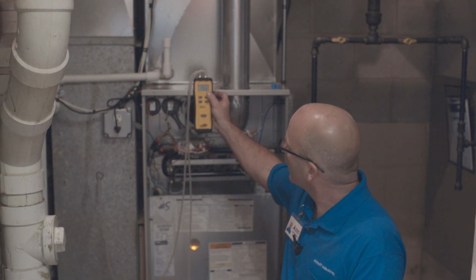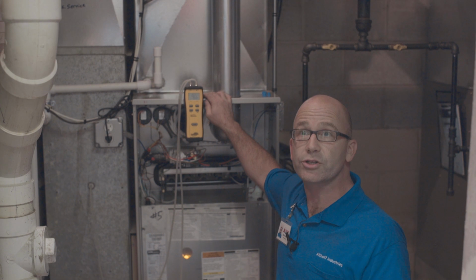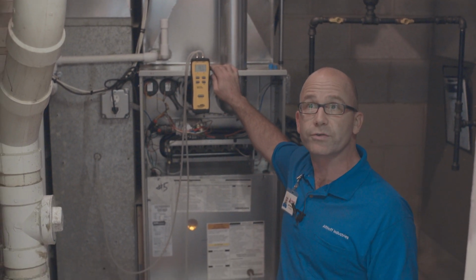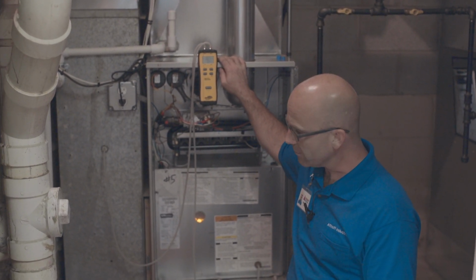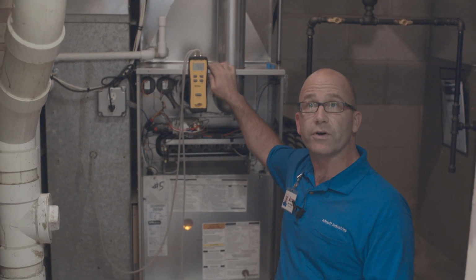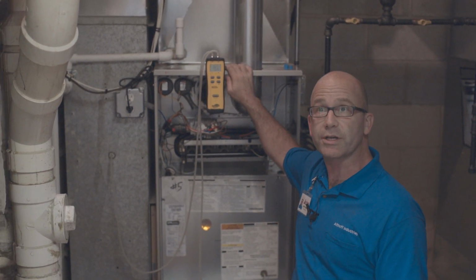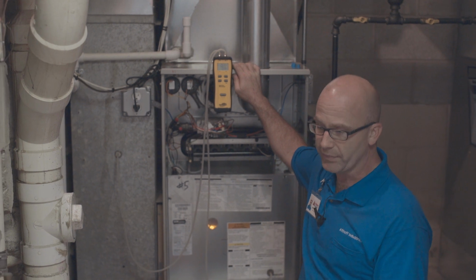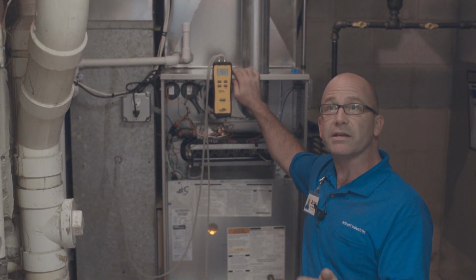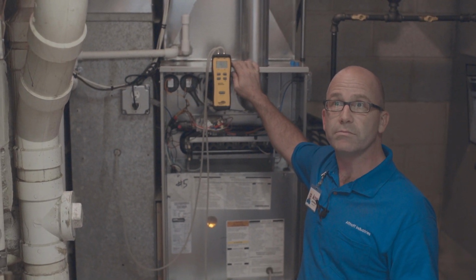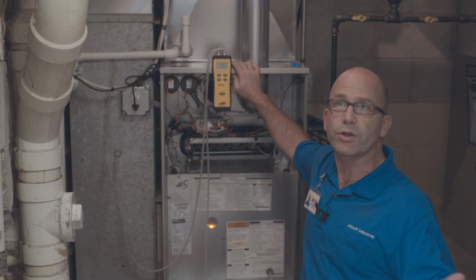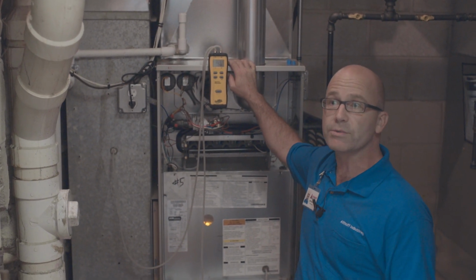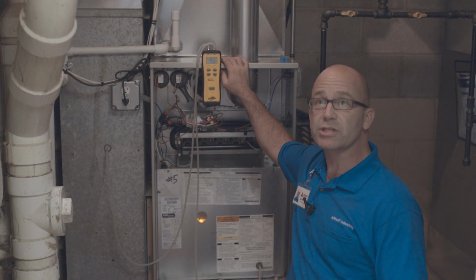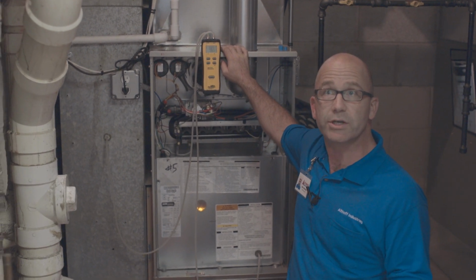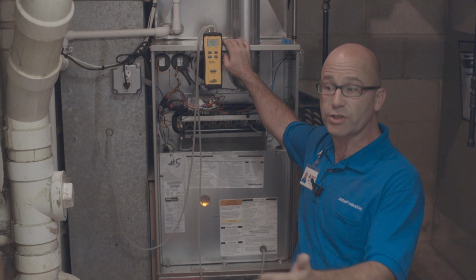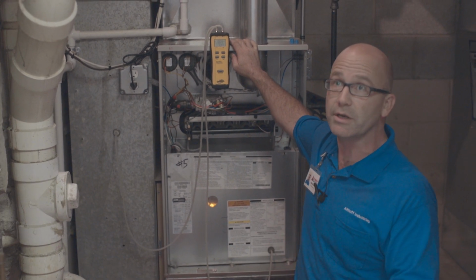There's kind of a joke in our industry. We call pleated filters sometimes super pleats. And all that means is the filter is good at catching dirt, particulate, and dust. It's great at that. But that also has a negative effect on the performance, meaning the operating condition of the system, whether it be an air conditioner or a furnace. Sometimes it can put a system over the top where it creates a no heat situation or a no cool situation by just having a dirty filter in the unit.